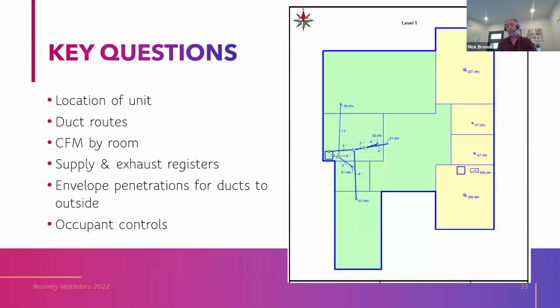So let me cover now in the last section how to install these a little bit. The key questions that come up are, where do you put the recovery ventilator? Where do you run the ducts? How do you know how much CFM per room? Where do you put supplies and exhausts? And how do you get the ducts out of your envelope? Handle those penetrations. And finally, what controls, if any, do you give the occupants?